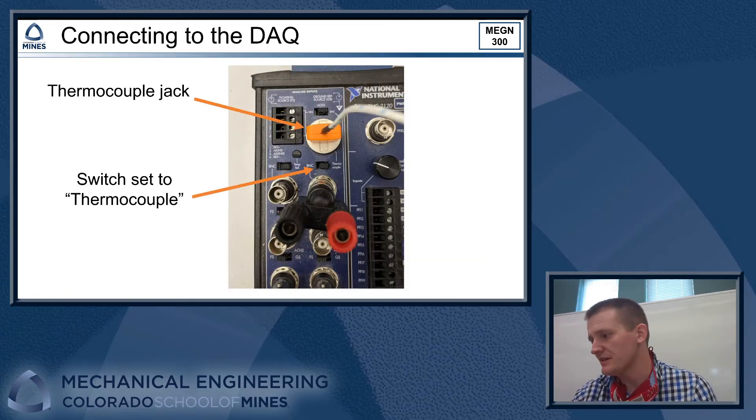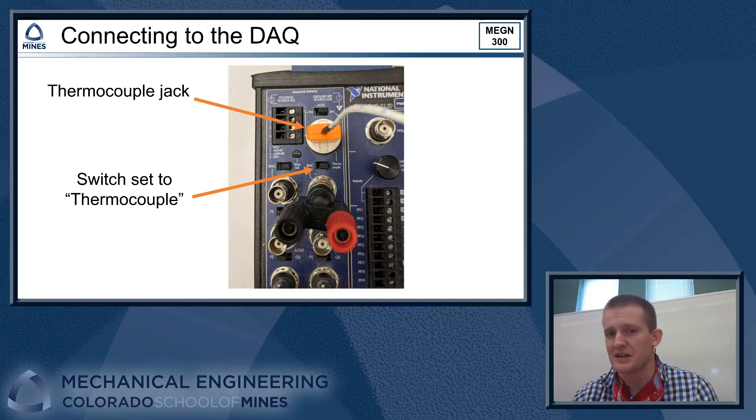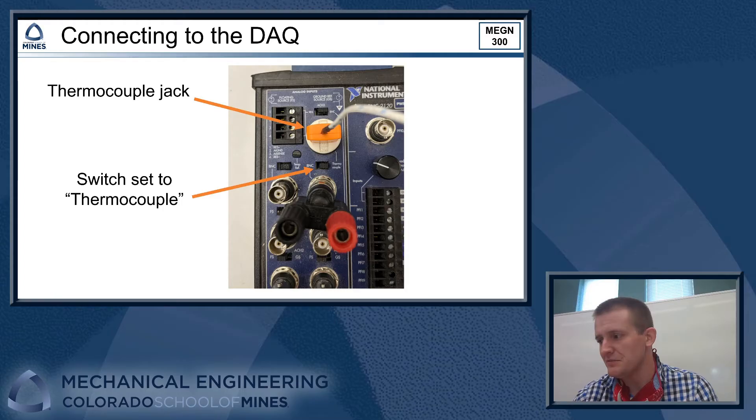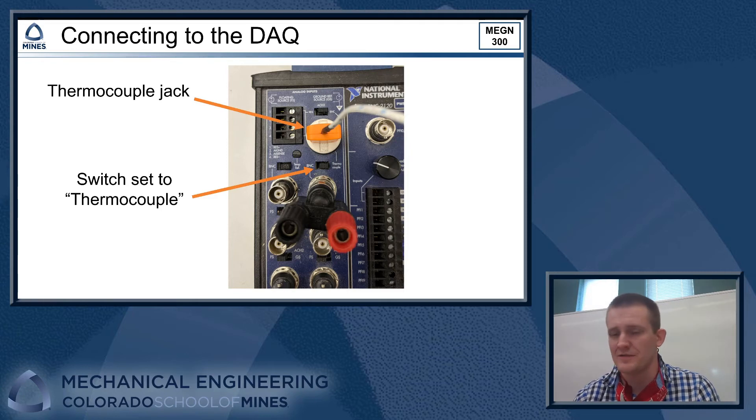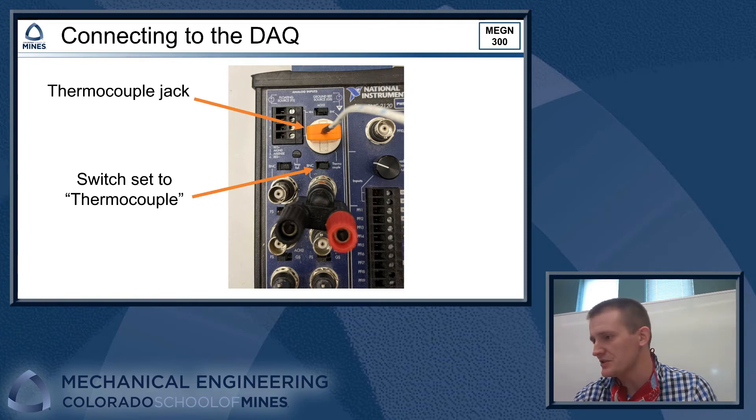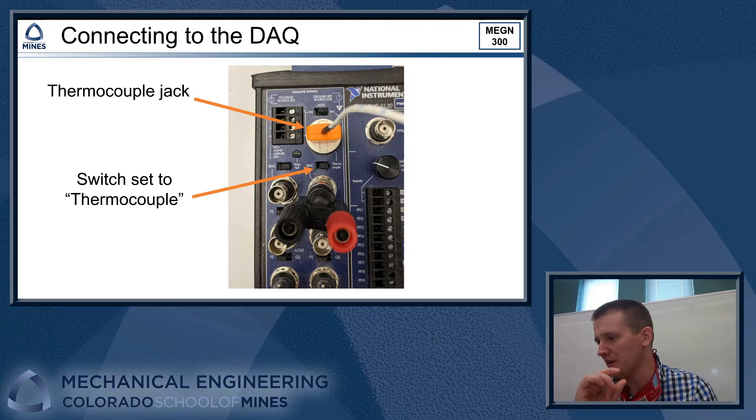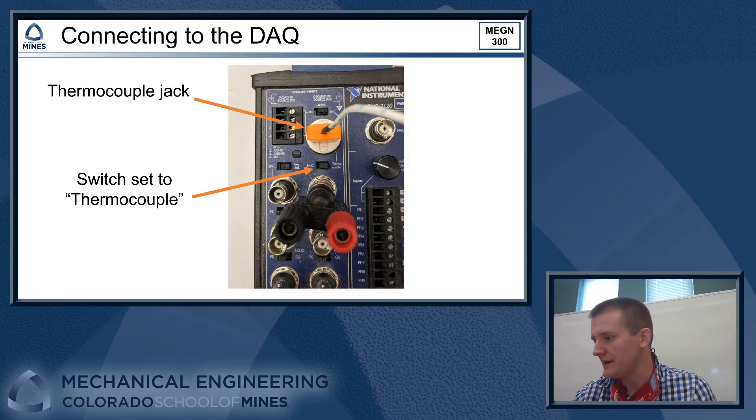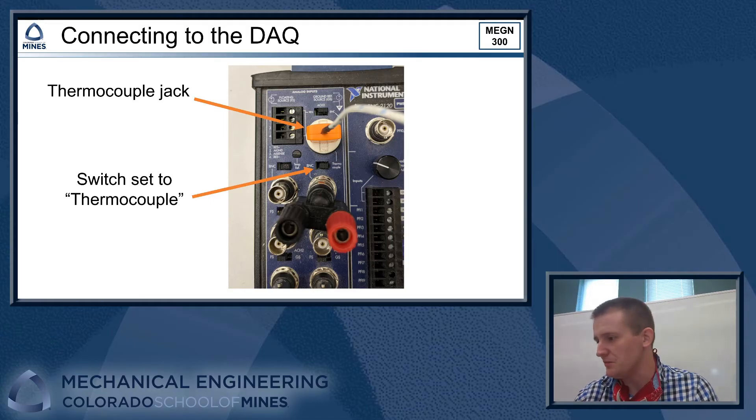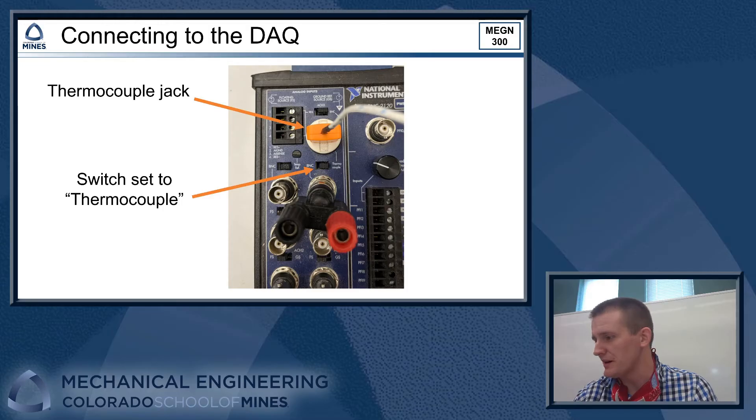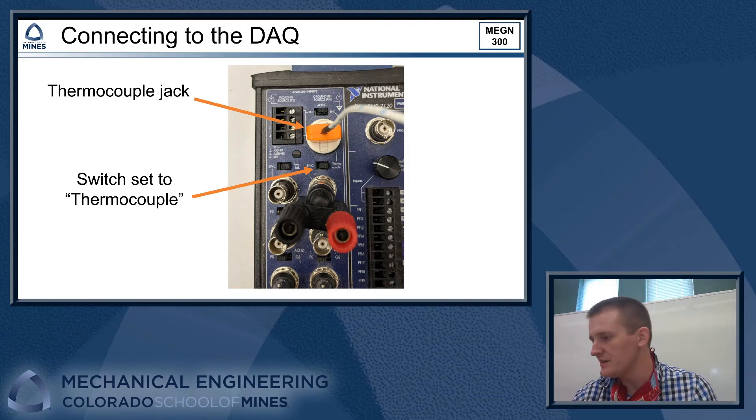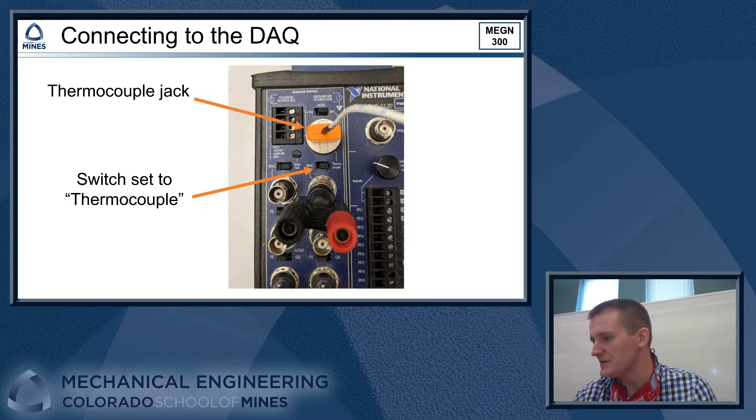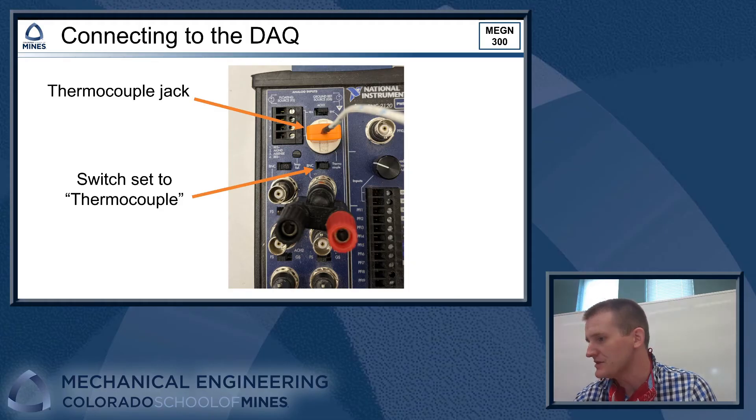So how do we connect this thing to the DAQ? Having this BNC accessory attached to your DAQ makes your life quite easy when we want to measure a thermocouple because it actually has a thermocouple jack built directly into it. If you take a look at the analog input section of your DAQ up in the top left-hand corner of the whole BNC accessory, you should see a white plastic plug. That is the thermocouple jack, and it's got a couple of little slots in there where you can plug the thermocouple in. It does only go in one way, so if you look carefully at the thermocouple, one of the plugs is wider than the other, so just make sure you line up the plugs with their correct holes so that it'll go in. If you feel like you're having to force it, it's probably backwards.